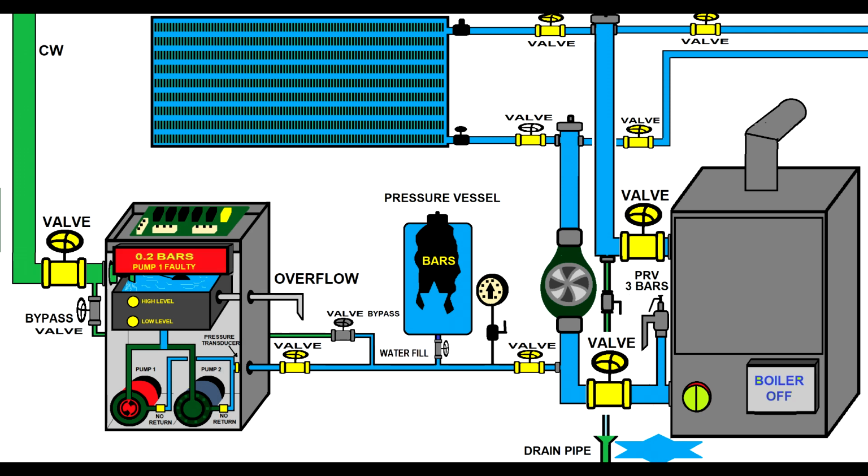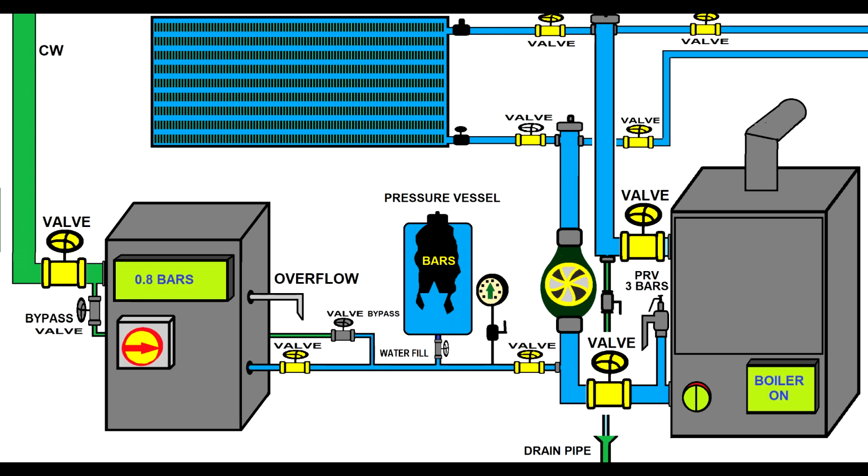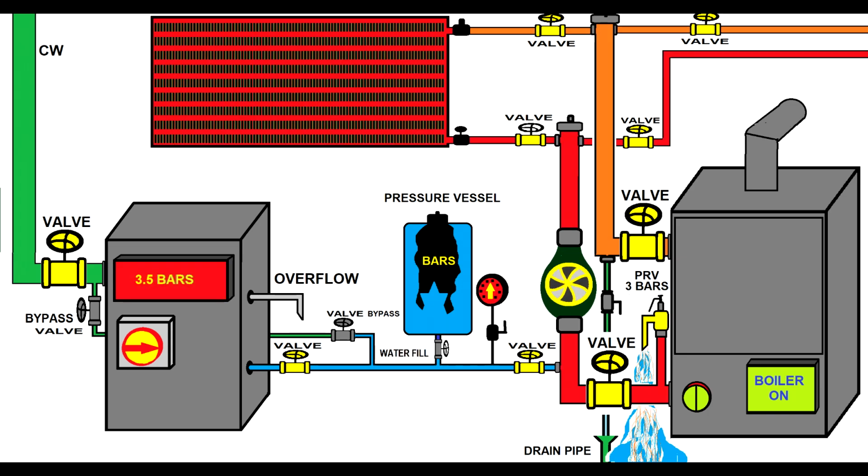If you damage a pump, an alarm will be triggered. You will see this alarm on the display of the pressurization unit, and the second pump will fill the system. It's not any problem, and you'll have a healthy system. Again, 0.8 bars, your system will run beautifully, and you'll be happy. But when the heating agent heats again, you start losing water again, because you never fixed the pressure vessel, which doesn't help.